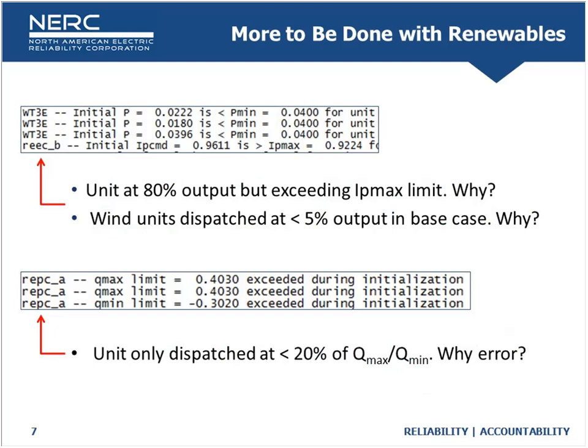Linking that to dynamics: if you pick up a base case off the shelf and initialize it, you can get a whole bunch of errors. For example, units operating at 80% of active power output yet exceeding their maximum real current command, or wind dispatched in the case at less than 5% — which raises questions about why you'd pick up a case at such a strange operating point.